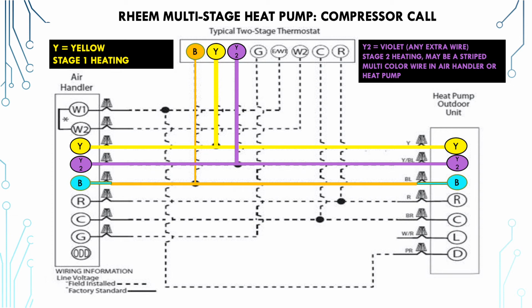I've seen a yellow with a black stripe. That's usually what you're going to see. So in this case, you have the yellow wire energized by the Y contact, which is your compressor call. So when they ask for heating, R routes power over to Y at the thermostat, and it's also simultaneously routing power to the B contact. So the reversing valve is energized to shift over to heating mode at the heat pump, and your first stage compression is energized, and then whatever control is dictating when the second stage compressor should engage, second stage heating engages with Y2 energized.